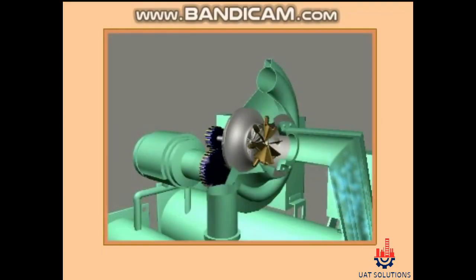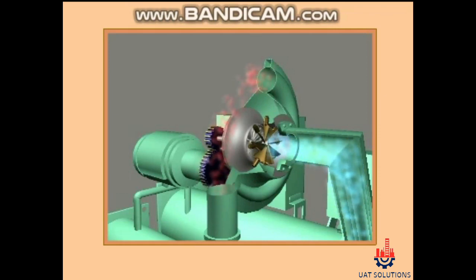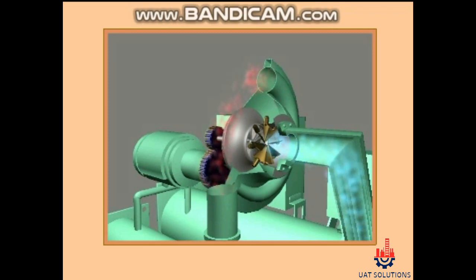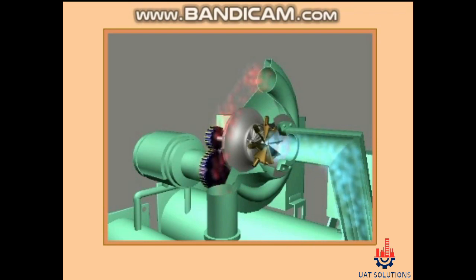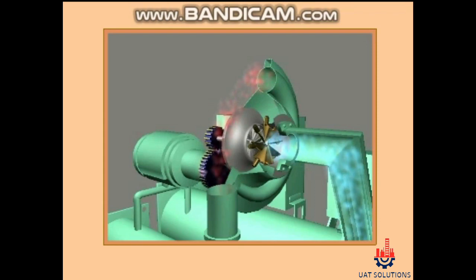Centrifugal compressor chiller package: liquid refrigerant boils in the evaporator and becomes refrigerant vapor. The refrigerant vapor then passes through the pre-rotation vanes and into the eye of the impeller. As the impeller rotates, the refrigerant is compressed and discharged into the condenser.